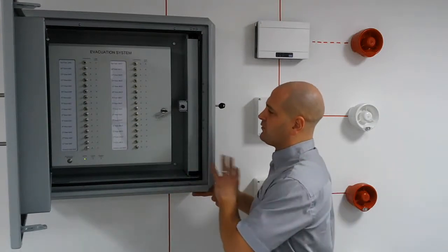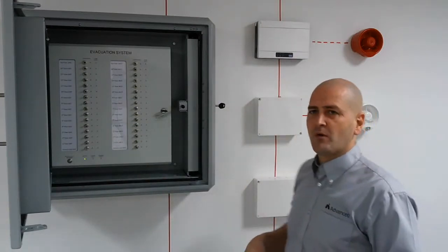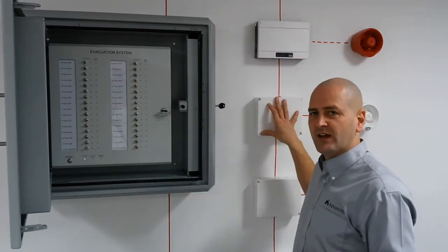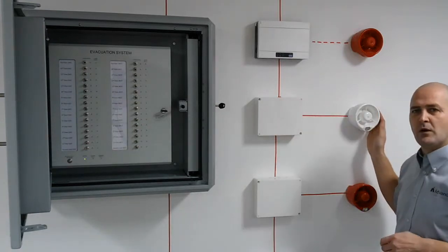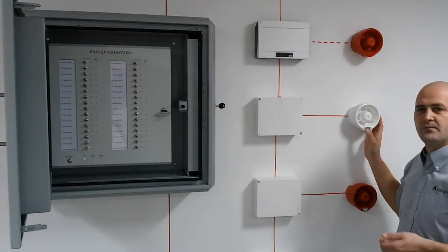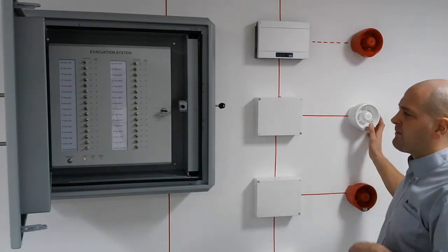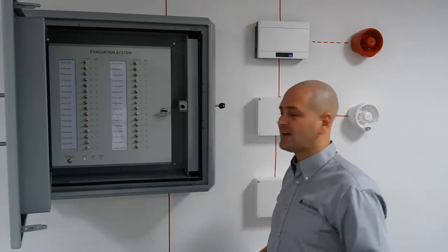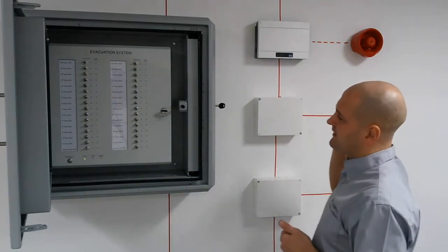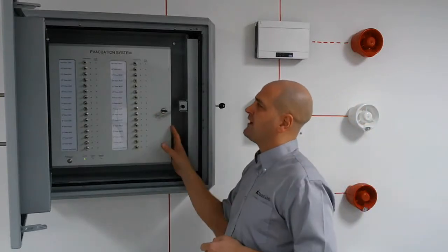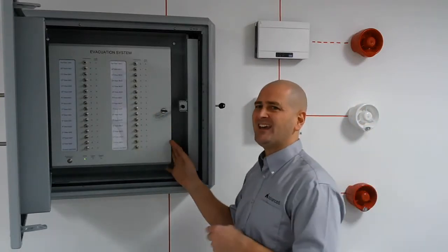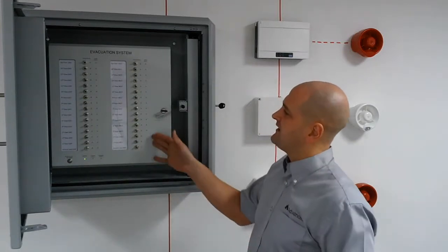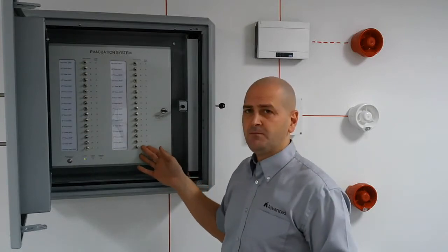Once we've got the panel, we're going to identify some typical components. So from your system design, we have a typical loop of devices, isolators outside the flats, and your sounder, your notification device, within the internals of the flat. Remember, everything to be suitably sealed. The recommended cable, typically enhanced cable, and the infrastructure will then obviously be reporting back to your control equipment, or your EACIE as it's known in industry. So this example is a typical 32 zone system. It could be any combination.